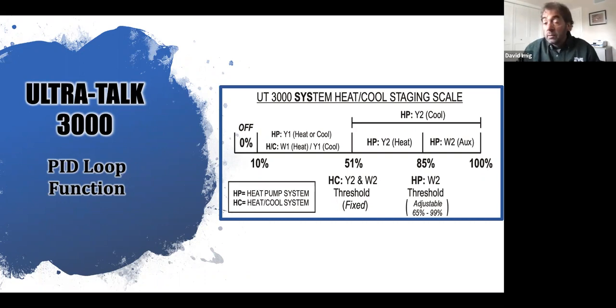Now, if I look at modulating equipment and inverter operation, it's a little bit different. First of all, my modulating furnace at the lowest stage is 50%, not 70%. My lowest continuous operating firing rate in a modulating furnace is 50% with a fan around 60%. That's my lowest operation. So if I come on at 36%, I'm still at 50% until I get to that point. If I haven't reached my target temp, I hit 51%, I take my equipment to 51%. I hit 52 because I haven't seen my target temp, my equipment goes up to 52%.